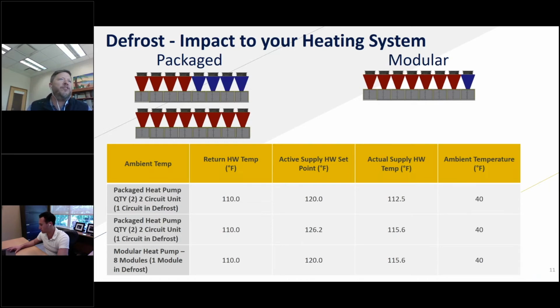And so when you evaluate it from this perspective, if maintaining hot water temperature into the space is critical or desired, then that really lends itself to saying, we need more smaller units rather than one or two big units, because by the reality of the design, you can't maintain that temperature with one or two big units anywhere near as well as you can with multiple smaller units.